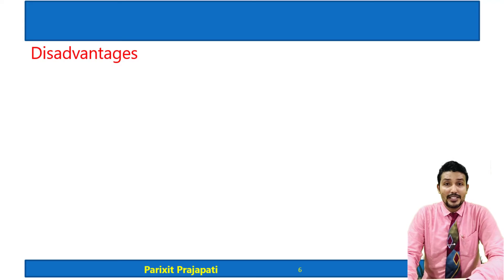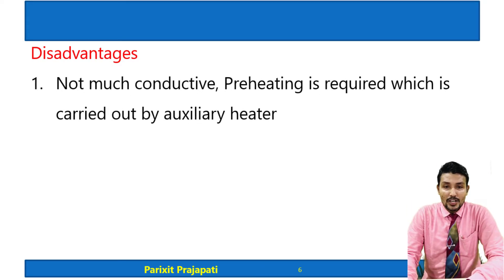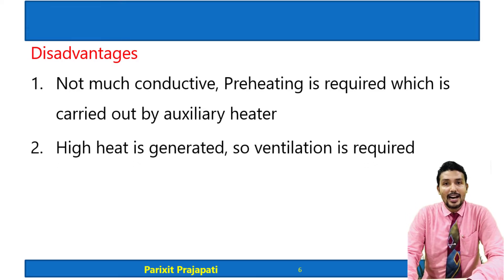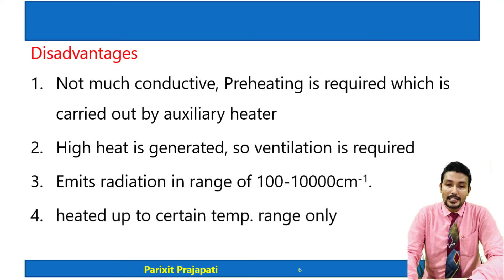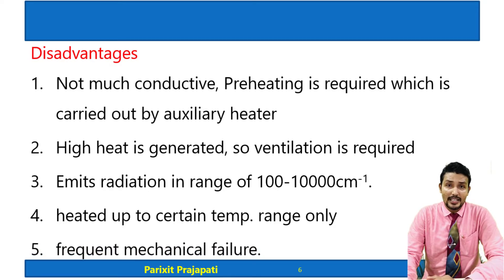The disadvantages of the Nernst Glower source are: it is not very conductive, so it requires pre-heating with the help of an auxiliary heater; high heat is generated so ventilation is required; it emits radiation only in the range of 100 to 10,000 cm⁻¹, so in some cases it is not useful; and there is frequent mechanical failure.